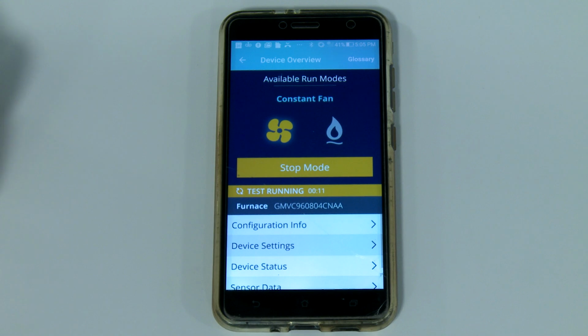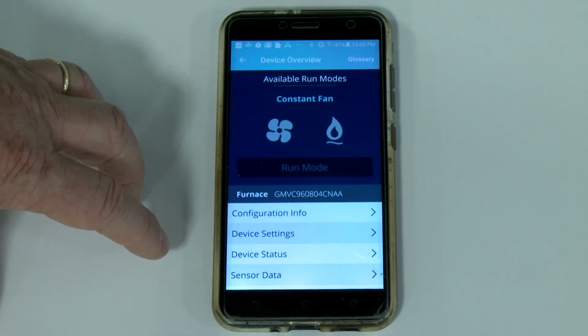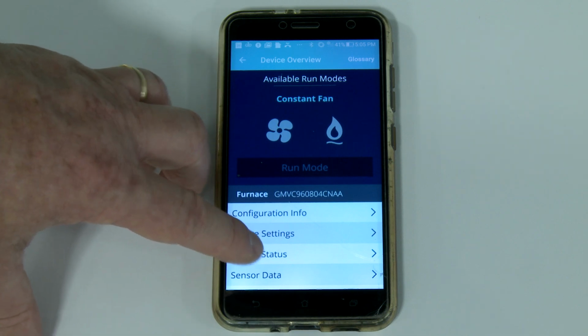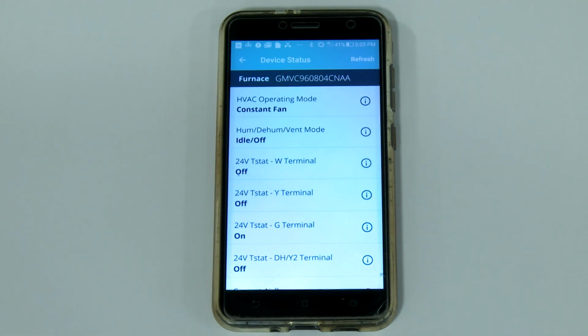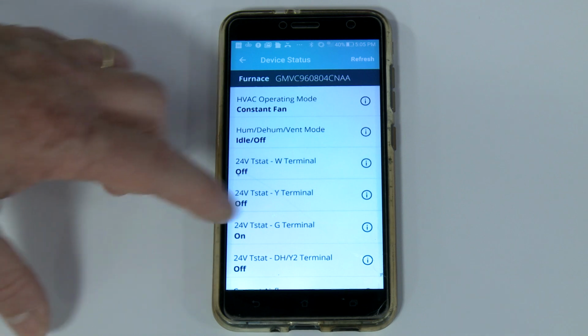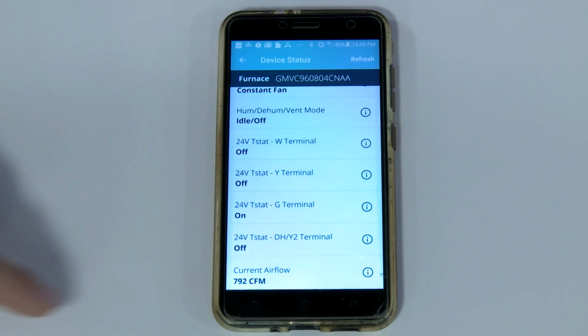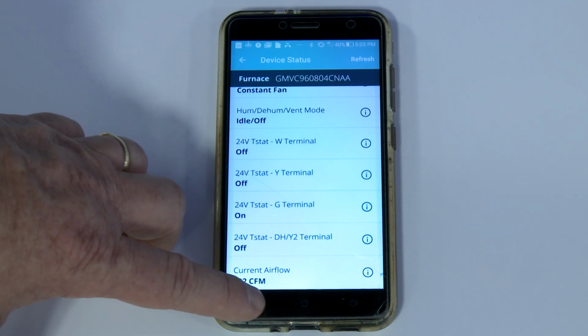Select Run, and the blower will start to operate until you hit Stop Mode, discontinuing the test. Moving down to the Device Status section, you can actually view the operating characteristics of the equipment. Very similar to the system menu you saw previously. Right now, the constant fan demand is displayed and the 24-volt thermostat G terminal is energized. If you scroll down, you'll find the current airflow that's being provided by the equipment.